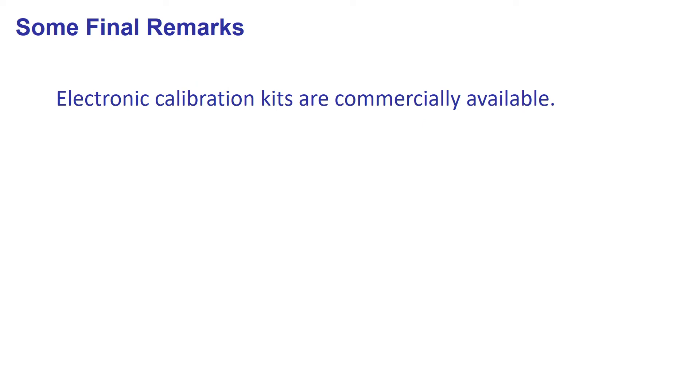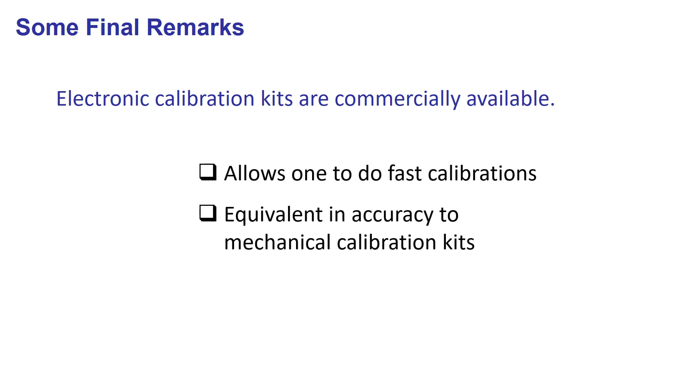Our network analyzer, like many other instruments currently in operation all around the world, only works with mechanical calibration kits. But it is possible to find other network analyzers with electronic calibration kits. They will offer you faster calibrations, but not better accuracy.